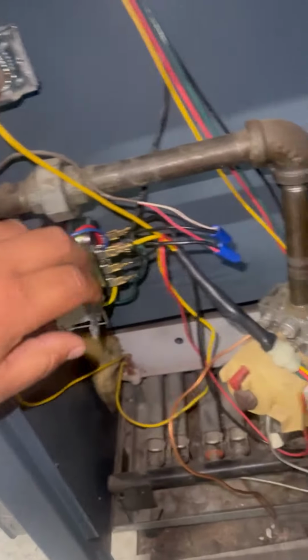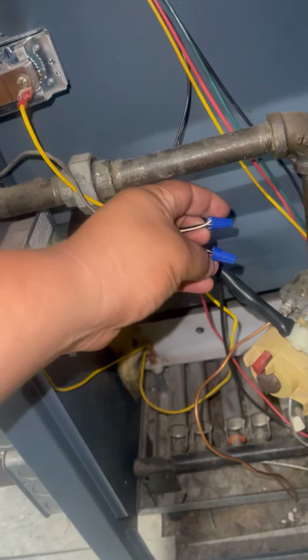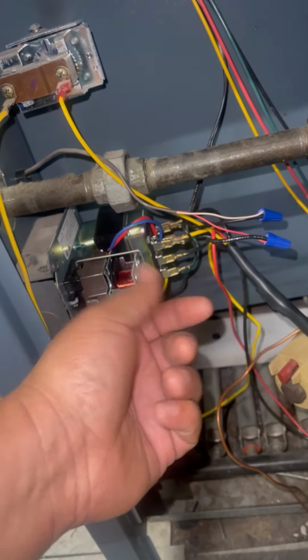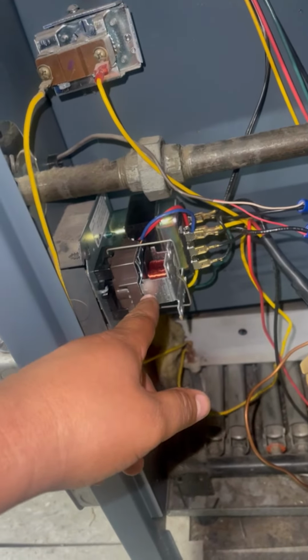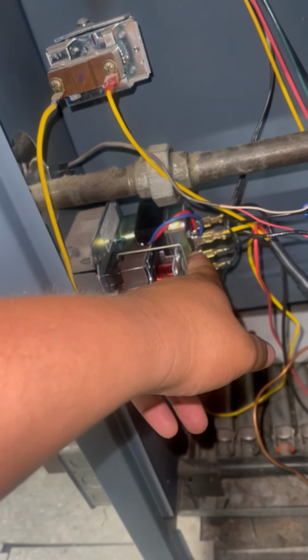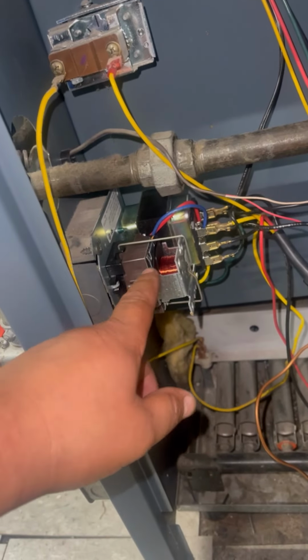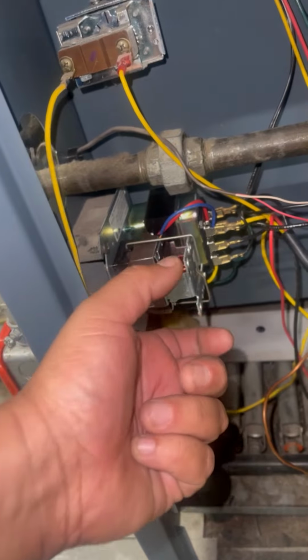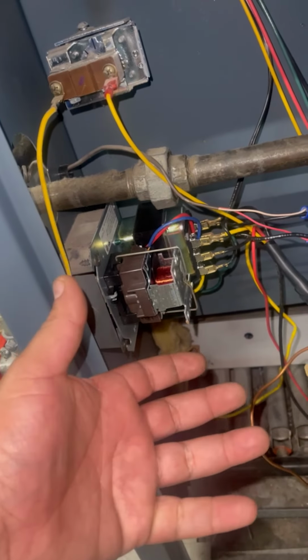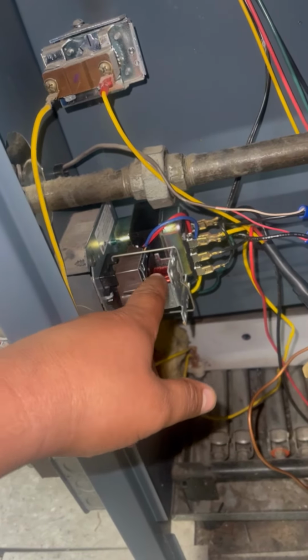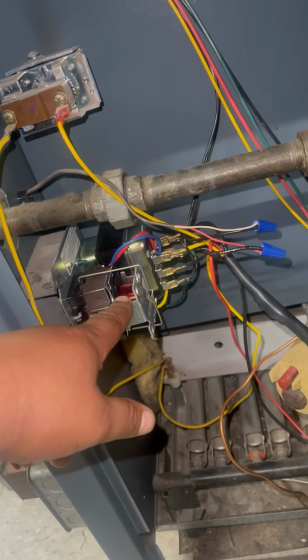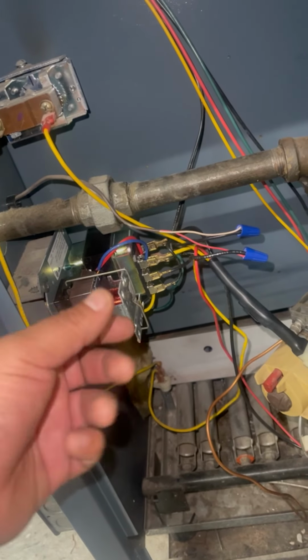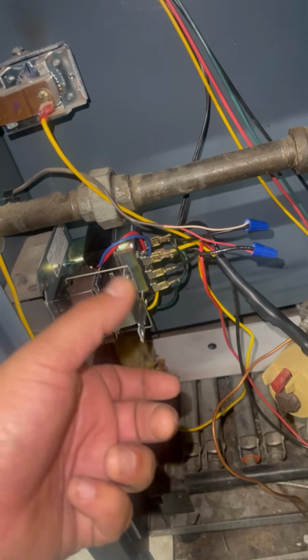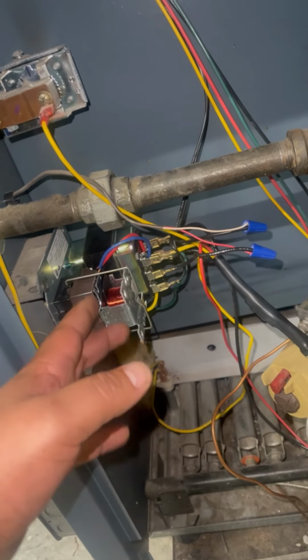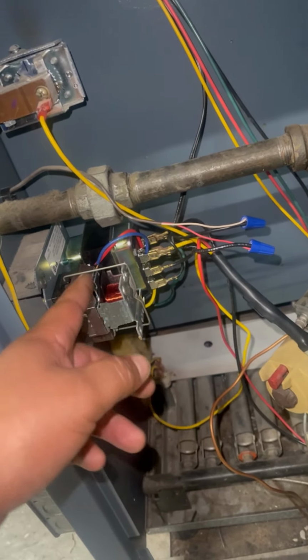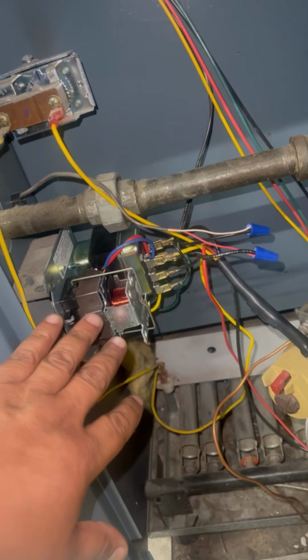So I know when I get these 2 end switches right here, or these 2 wires, when I touch them together, it's supposed to chatter, meaning the relay is supposed to pull in. So it's not pulling in, but I'm getting 24 volts. So I take it one step further. I take this out. First, I noticed that when I take it apart, it's really, really hot. It usually is an indicator that this relay is probably bad, meaning the coil. But the second thing is, it's not the relay. It's just not passing the power. That's what it really does. It directs the power. And I put a jumper and it turned on. So right away I knew the relay was bad.